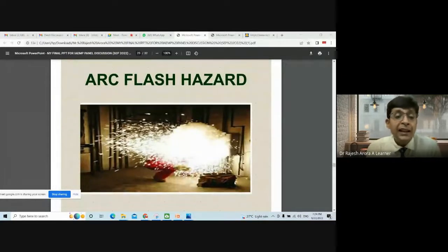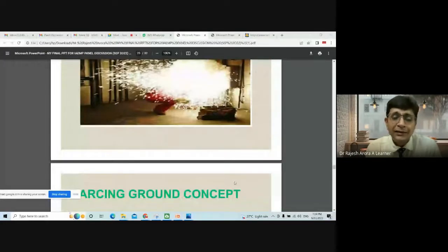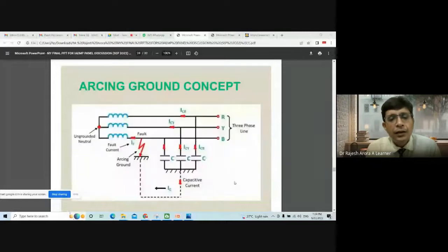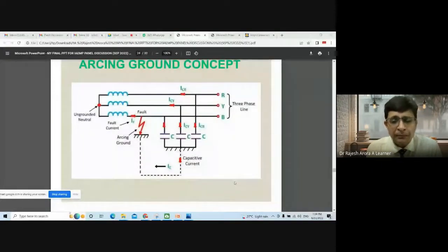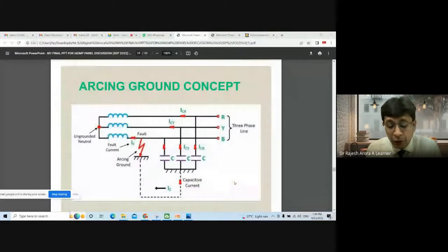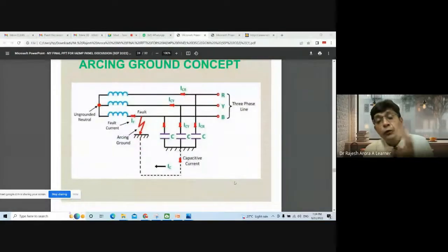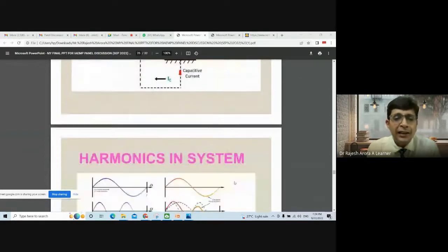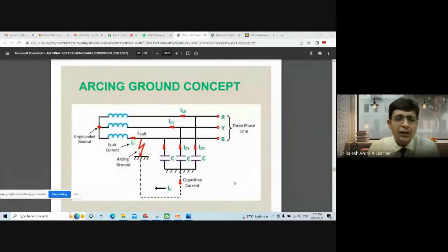Avoid sparking because of poor insulation and loose contact. You have to avoid it. Otherwise, there may be arc flash. The arcing ground concept comes when the earthing system of the utility's distribution transformer becomes loose, or is removed. In that case, the voltage of the sound, healthy phases becomes double, or equal to the phase-to-phase voltage, and your gadgets start failing. And that is not in your hand. Only overvoltage protection can protect all these things.